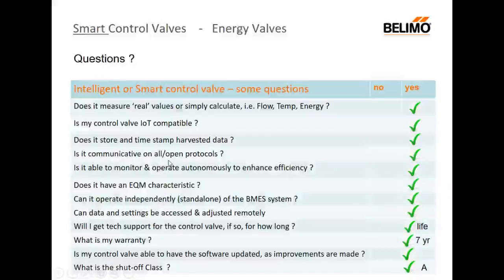Is it communicative on all open protocols? Because some smart valves may be tied to a particular controls company and you don't want necessarily to be tied. You may, but you may not. And an open protocol is going to give the building owner the freest choice of how he accesses that information. Is it able to monitor and operate autonomously? Because that's incredibly valuable for ongoing continuous commissioning and maintaining system efficiency.